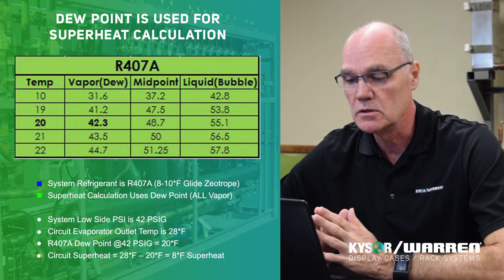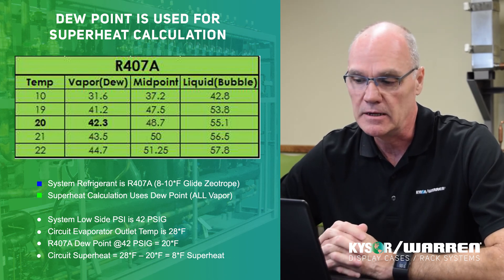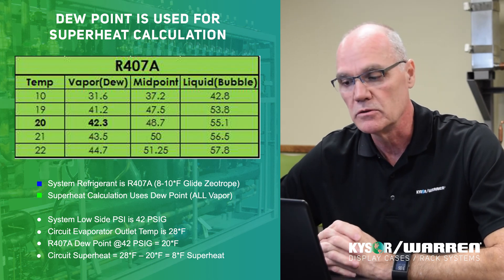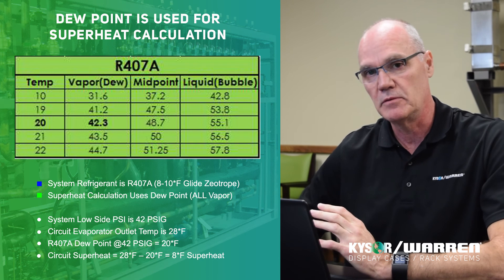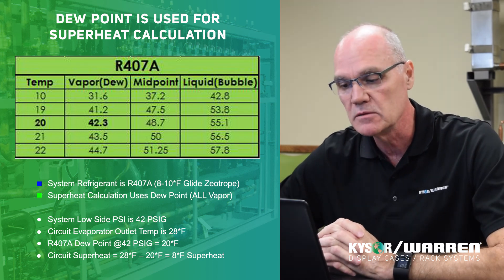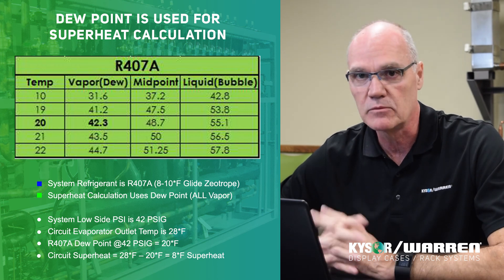If you set your superheat and set the system up on bubble point, you're going to have a very unhappy system and an unhappy customer. You're either going to be maintaining temperatures well above the set point, or most likely — depending on how you adjust your superheat — you'll have a system with flood back, potentially damaging your compressor. So that's a quick tip on high glide refrigerants, how they differ from zero or low glide refrigerants, and what that means when setting superheat in an evaporator. Thank you.